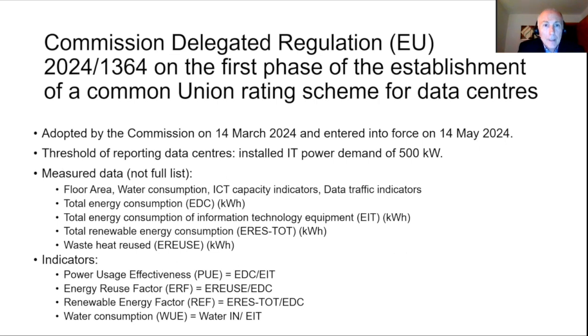Following this initial requirement in the Energy Efficiency Directive, the Commission adopted a delegated regulation, published in May this year and now in force, which established the first phase of a common rating scheme for data centers and defined the reporting requirements introduced by the directive, listing all the measurement data to be submitted regularly by data center operators with installed IT power demand above 500 kW, together with other important indicators.